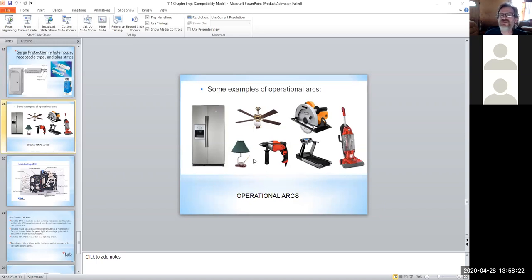So what is operational in-rush current? You turn the device on and it has an instantaneous rate of charge, meaning it pulls more current when it's first turned on, powering up, and it rises. If normally the thing pulls 5 amps, when you first fire it on, it could rise up like 30 to 50% over that, where your 5 amp device shoots up to like 7 or 8 amps. That's its instantaneous rate of charge. It settles down once it's running, typically with motors because of the coils involved, but lamps as well - anything you're energizing has this instantaneous rate of charge.